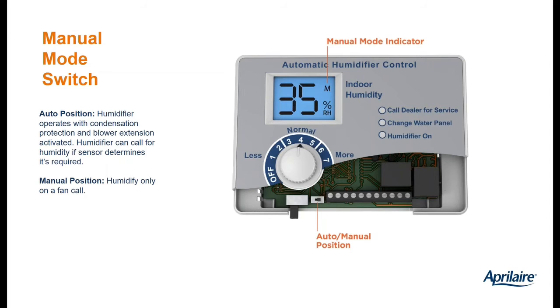And then inside the carton that the Model 60 came in, there's a little sticker that you would apply to the humidistat that covers up the off 1, 2, 3, 4, 5, 6, 7 numbers and replaces it with a scale so that the consumer can adjust that knob to match up with what the outside temperature is. So you get the lowering of the RH when it's very cold outside and the increase in the RH set point when it's more mild outside.